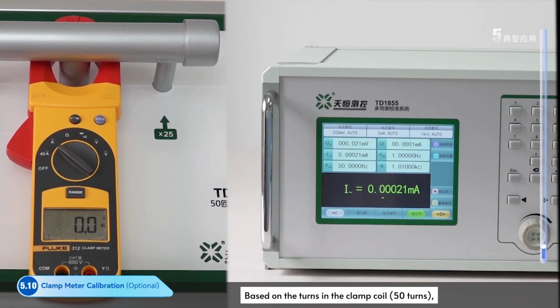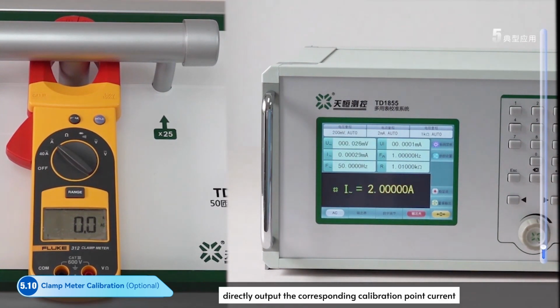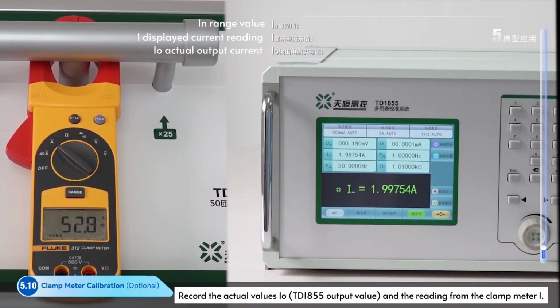Based on the turns in the clamp coil, 50 turns, directly output the corresponding calibration point current. Record the actual values and the reading from the clamp meter.